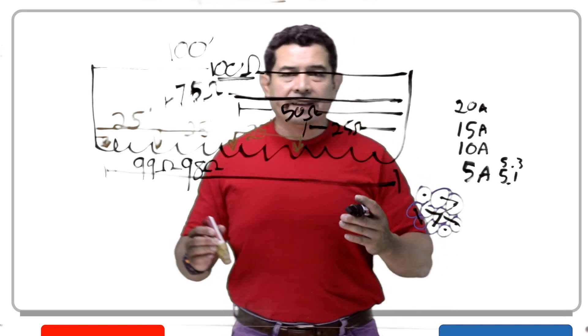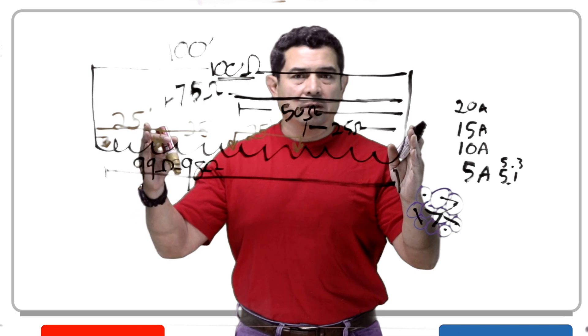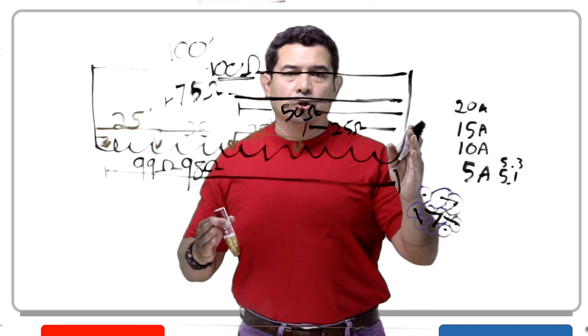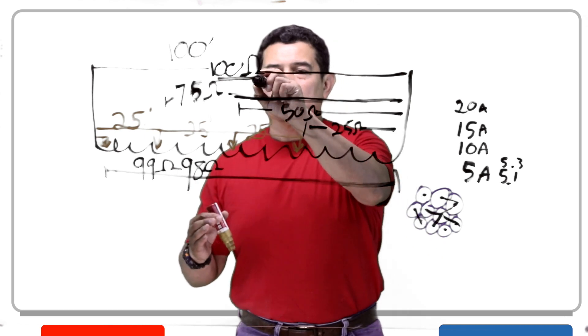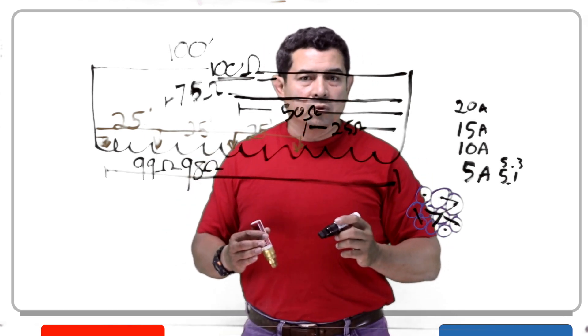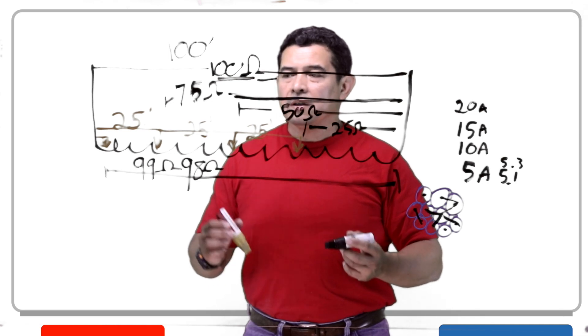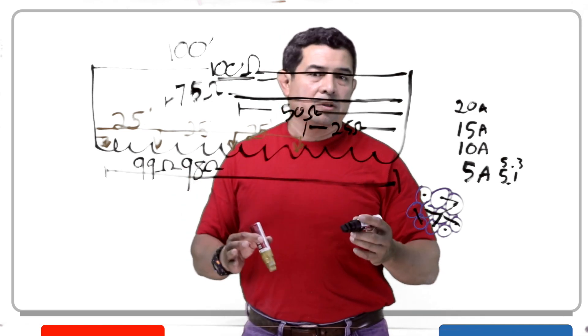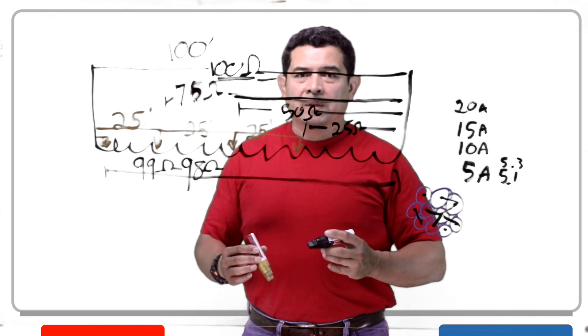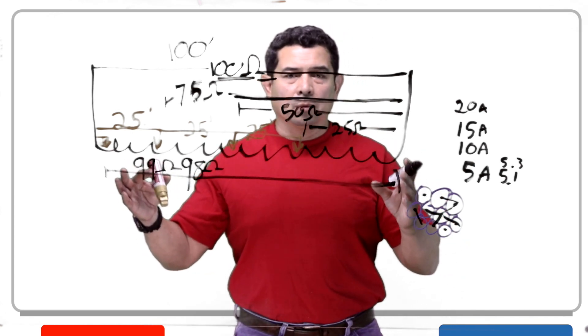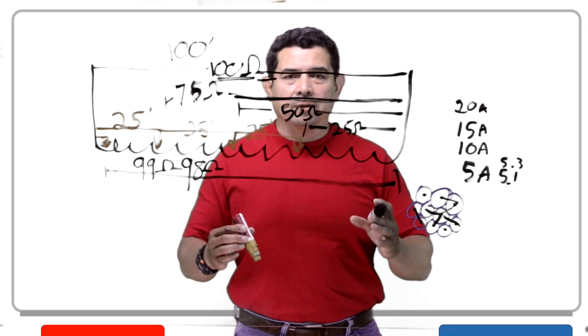So let's talk about this again. We said that a short is when you shorten the path. Whether it is by one or two ohms or 25 ohms, 20 ohms, 10 ohms, you still have a short. So that is a short. When you shorten the path, the only way to know that you're shortening the path is by checking your resistance, by checking the ohms. And what are you going to compare it to? Hopefully with what the original reading was. If you don't have the original reading, then hopefully you will have a motor by the same model number, same manufacturer, and then you can check the resistance on that and compare that to what you have. But these are all things that you might want to do to a brand new motor. And again, depending on the size of it, if it's a large motor, you would definitely want to do this. Keep an eye on it so it doesn't fail on you.